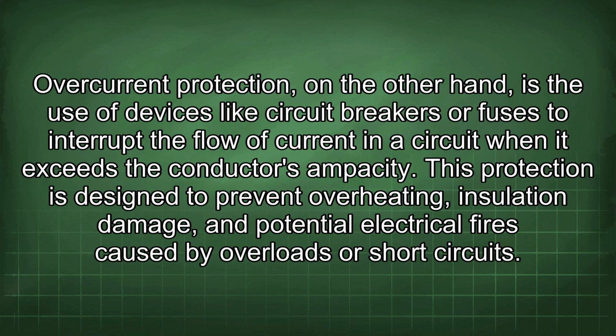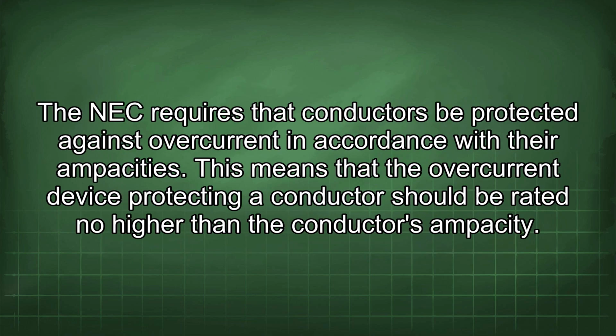Overcurrent protection, on the other hand, is the use of devices like circuit breakers or fuses to interrupt the flow of current in a circuit when it exceeds the conductor's ampacity. This protection is designed to prevent overheating, insulation damage, and potential electrical fires caused by overloads or short circuits. The NEC requires that conductors be protected against overcurrent in accordance with their ampacities.